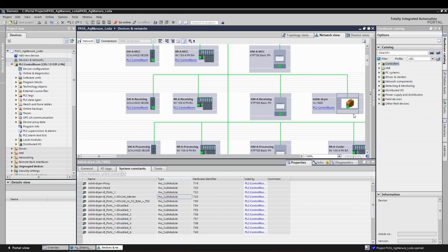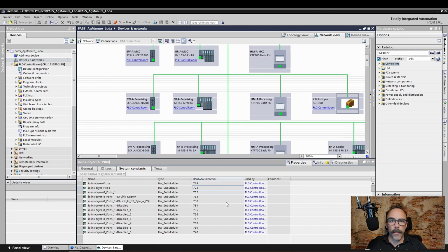Now that means if you're using an IO-Link device, you use the hardware ID of the individual device, not the hardware ID of the gateway itself, unless you were trying to access diagnostic data from the gateway. So with that, you pretty much know all you need to know in order to get started bringing in record data from I/O devices. Those devices can be anything from radioactive density gauges to RFID sensors out in the field. And all of this data is available simply by using the read record functionality.